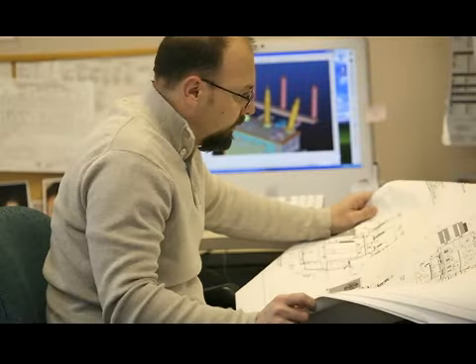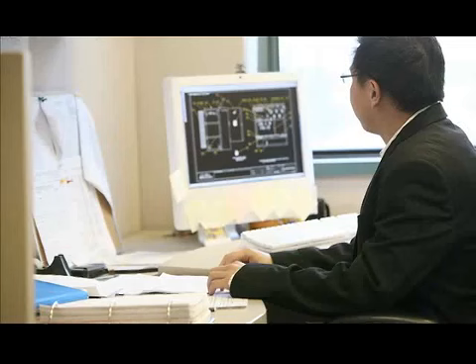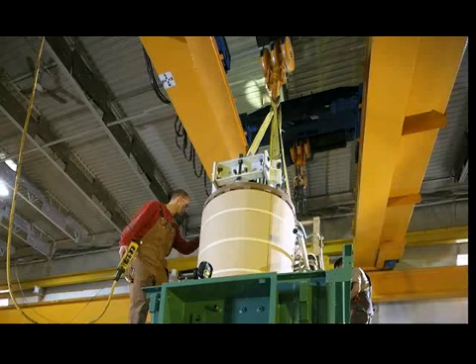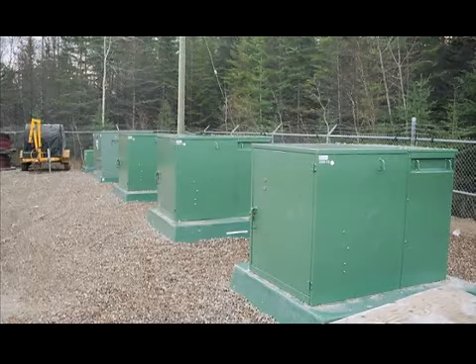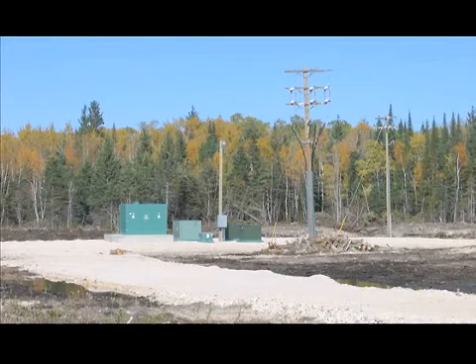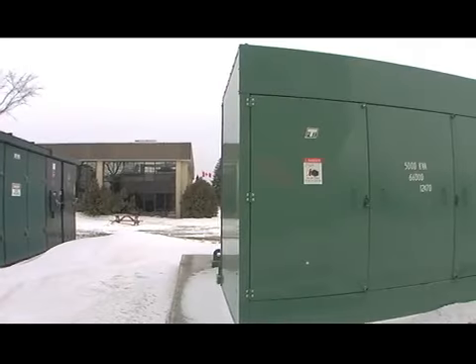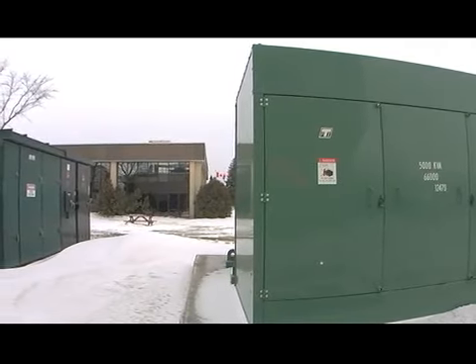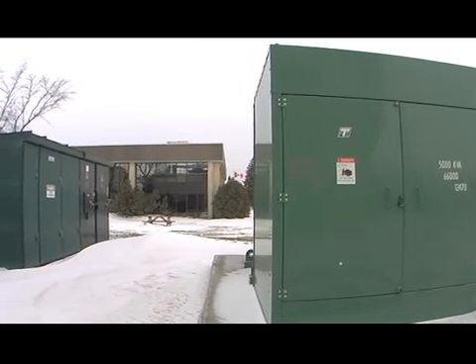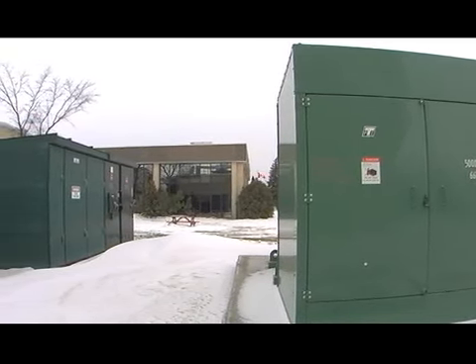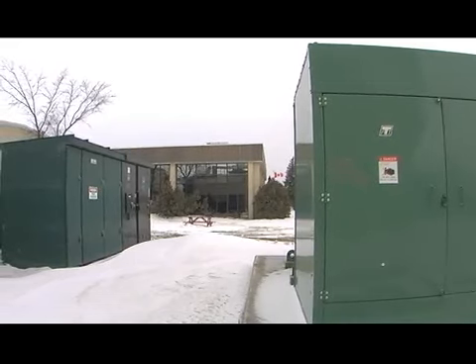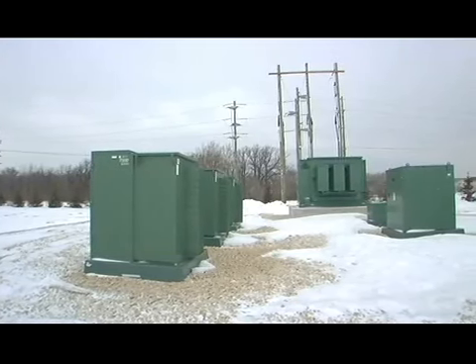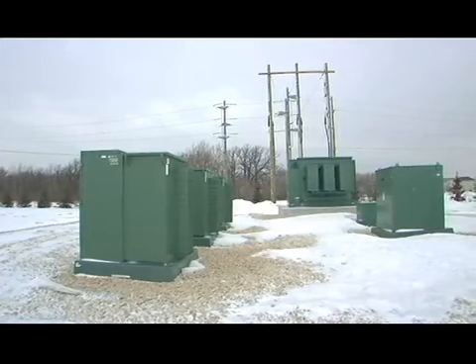The high voltage Padmount is designed and engineered at PTI's manufacturing facility. This in-house design division allows for greater flexibility in transformer manufacturing. Utilities can work in partnership with PTI to create custom solutions for their distribution networks. The design of the high voltage Padmount allows for modular building. The units can be placed parallel to each other to create any combination of load capacity or number of feeders required for a particular situation.